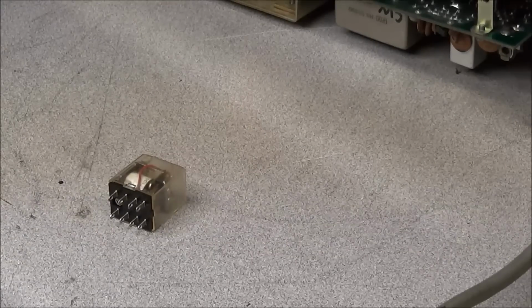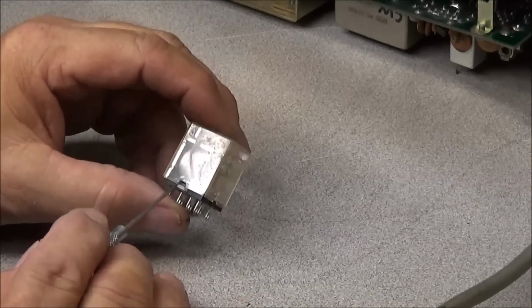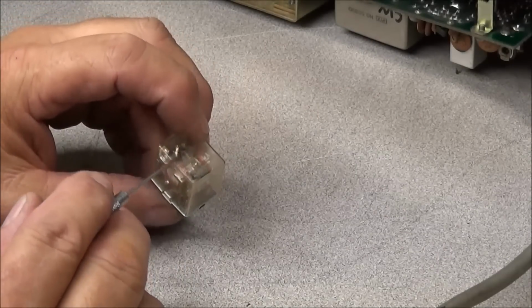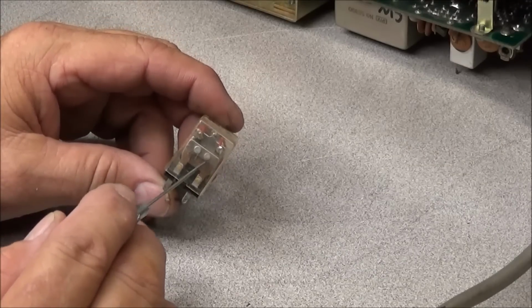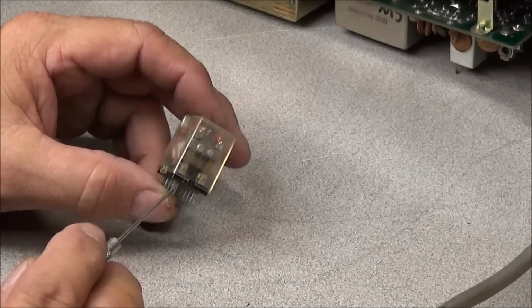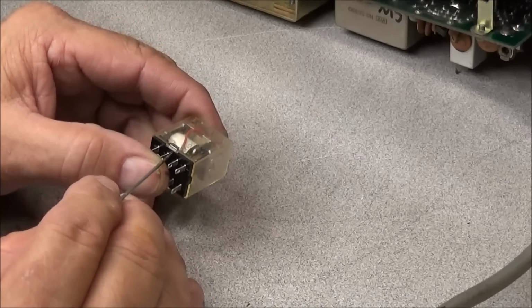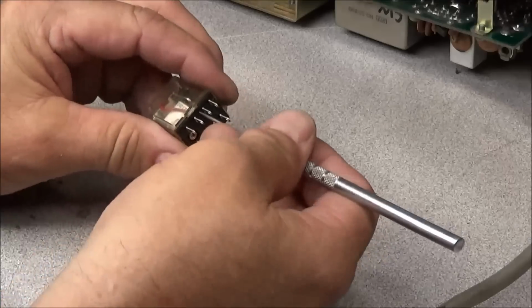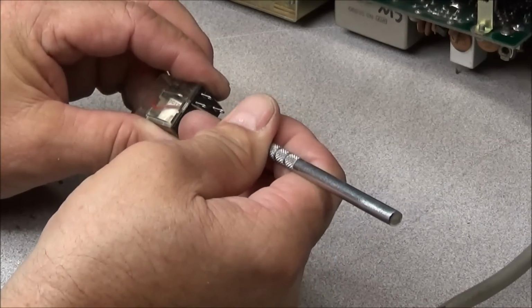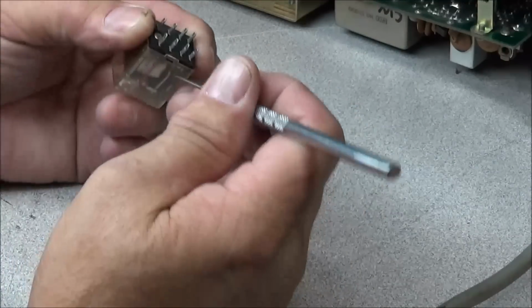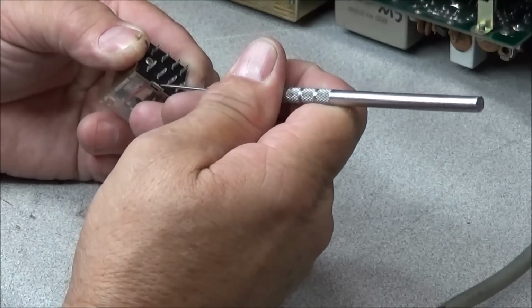I got the relay out, and what we're going to do is pull the case off of it, remove the spring, and pull the pivot point out to have a look at the contacts on it. To do this, just pop these tabs and hold the base of it.